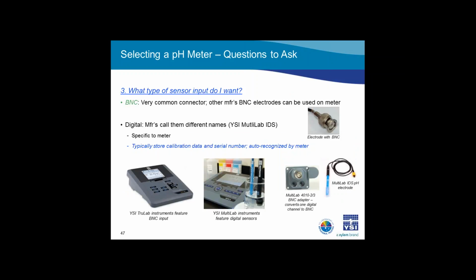After narrowing your search based on parameters and the number of channels, I would further narrow it by considering the type of sensor connection you need. BNC is perhaps the most common type of connector. One major advantage to this sensor is how universal it is. Typically, BNC electrodes can be connected to any pH meter with BNC input, regardless of the manufacturer. So another manufacturer's BNC electrode can be used on our TruLab, and our BNC pH electrodes can be used on other manufacturers' BNC pH instruments.